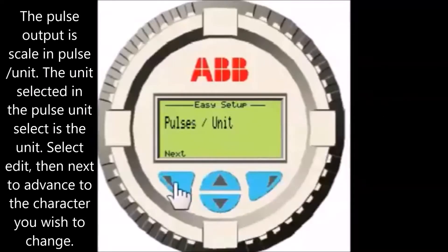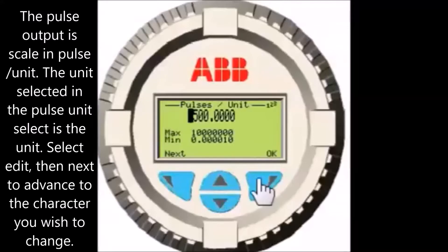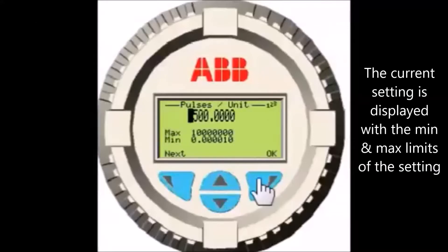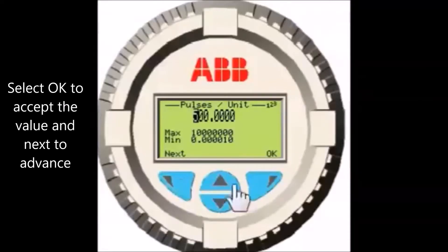The pulse output is scaled in pulses per unit, the unit being the unit selected in the pulse unit selection. Select Edit — the current setting is displayed with the minimum and maximum setting limits; these limits cannot be exceeded. Select Next to advance to the character you wish to change and use the up and down arrow soft keys to change the value. Select OK to accept the value and then select Next to advance.